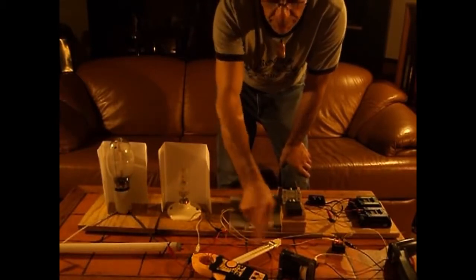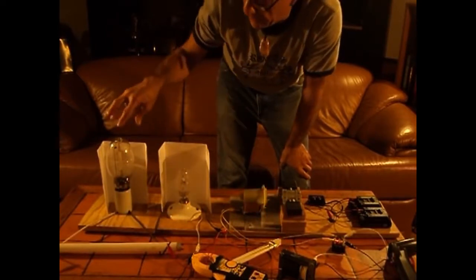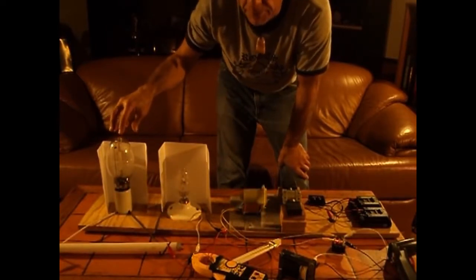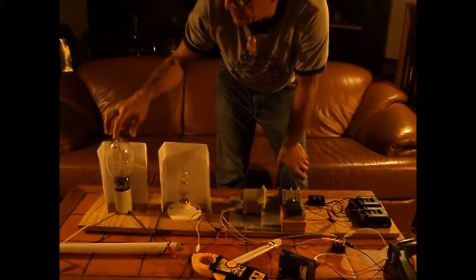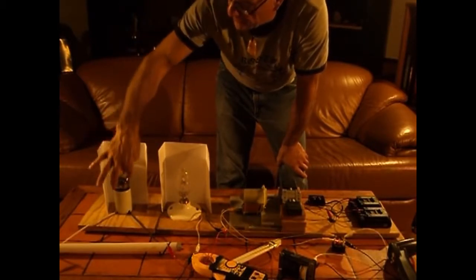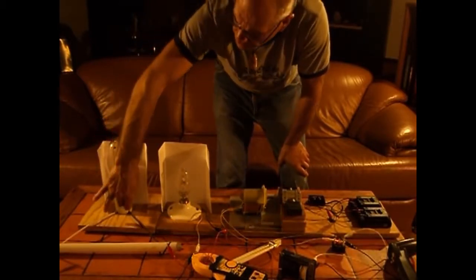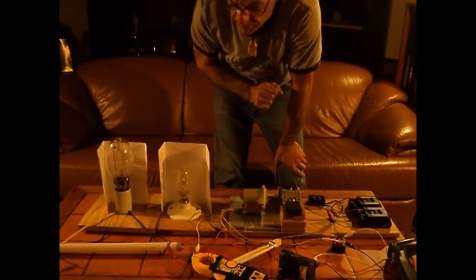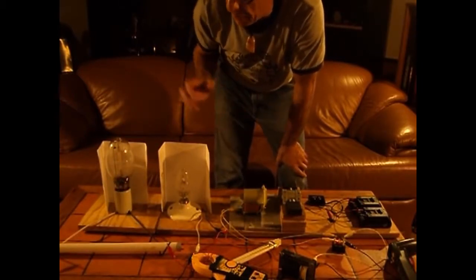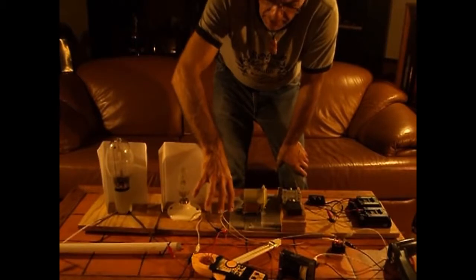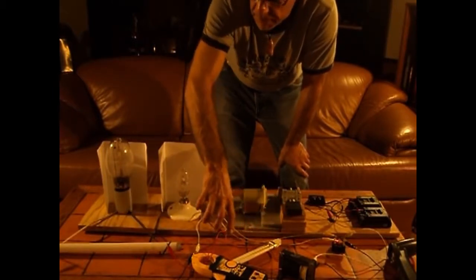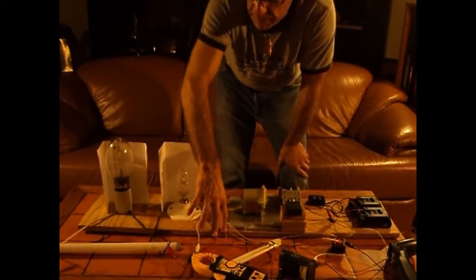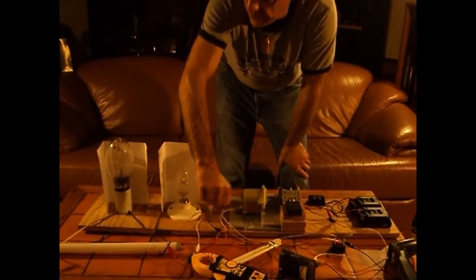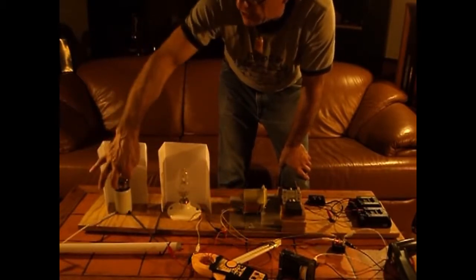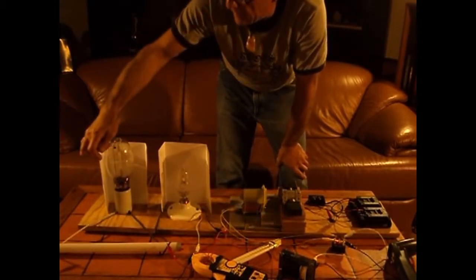We'll be able to read the amperage since I'm creating an extreme draw, because the arc jump is 3 inches plus another half inch underneath the bulb. So I can pick up a lot of draw and calculate how many amps this thing is pushing at full maximum voltage to make this massive jump on the element, because that's high pressure sodium.